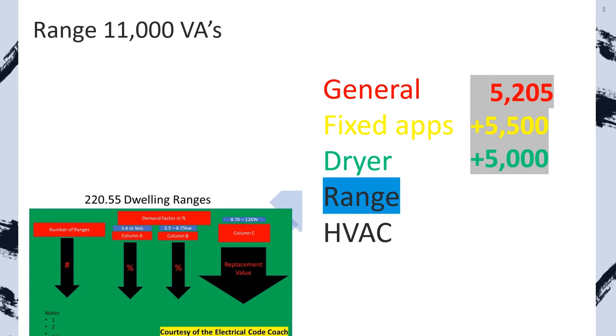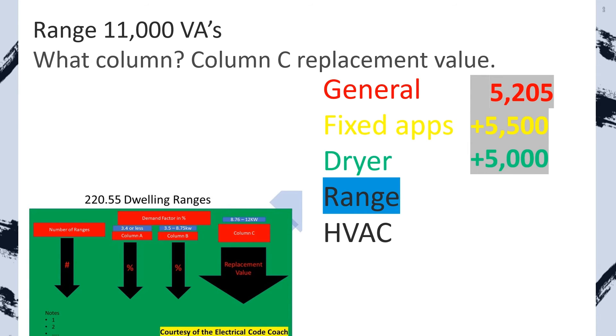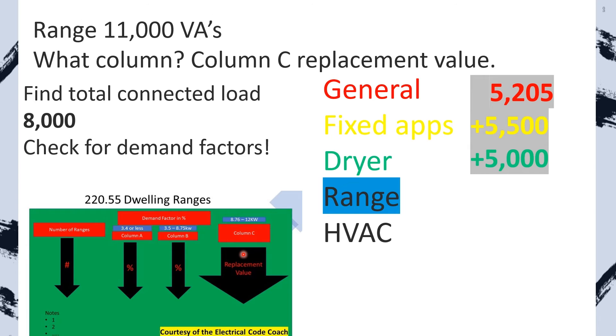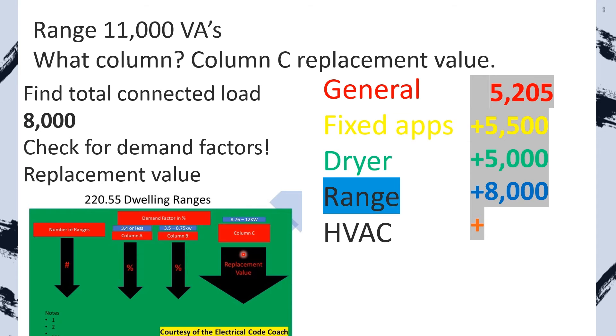Now our range. The first thing we're going to ask is what column does our individual range fall in? This one falls into column C, and column C is a replacement value. Let's find our total connected load — we start on the left-hand side of the table, find our number of ranges, then cross over to column C, and it's 8,000. Now we check for demand factors: there are no demand factors on column C because it is a replacement value, and we write down 8,000.